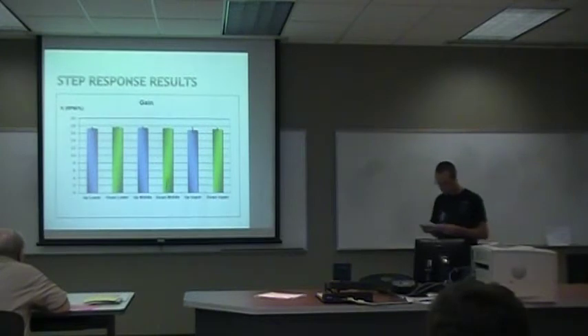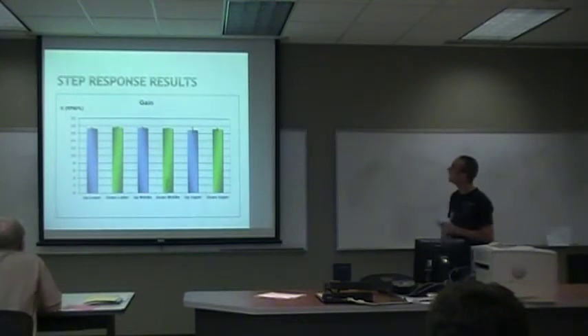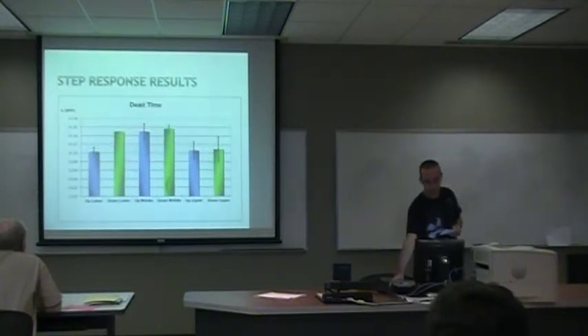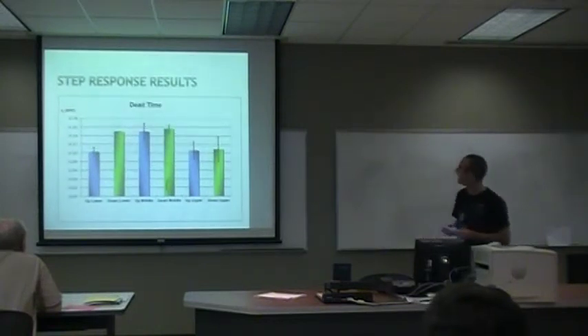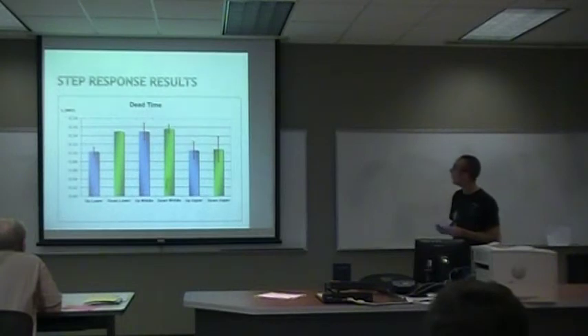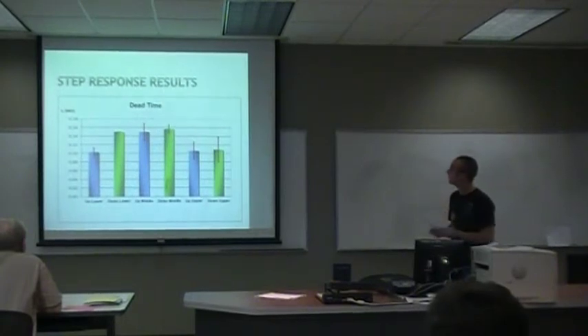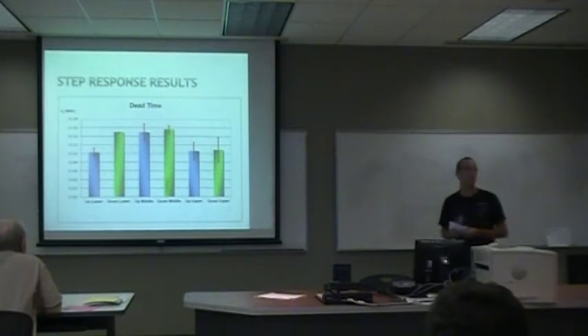These are the step response results for the model that I've just showed you. The gains don't vary very much. They're right around 17.4. The dead time is much longer for the first two regions, and for the upper region, it's a lot shorter.